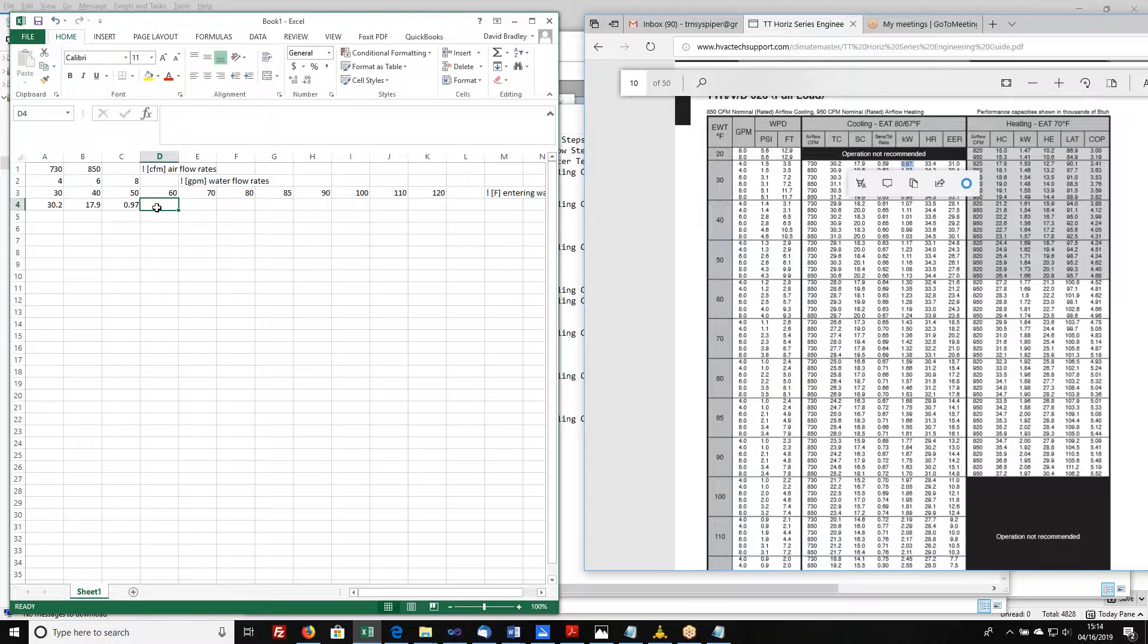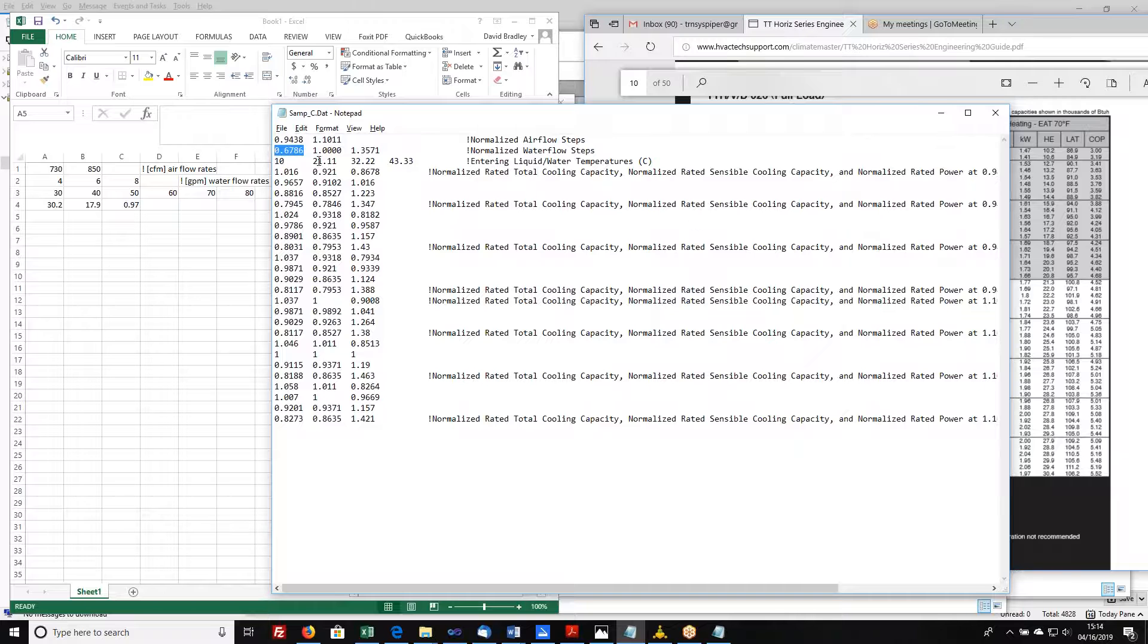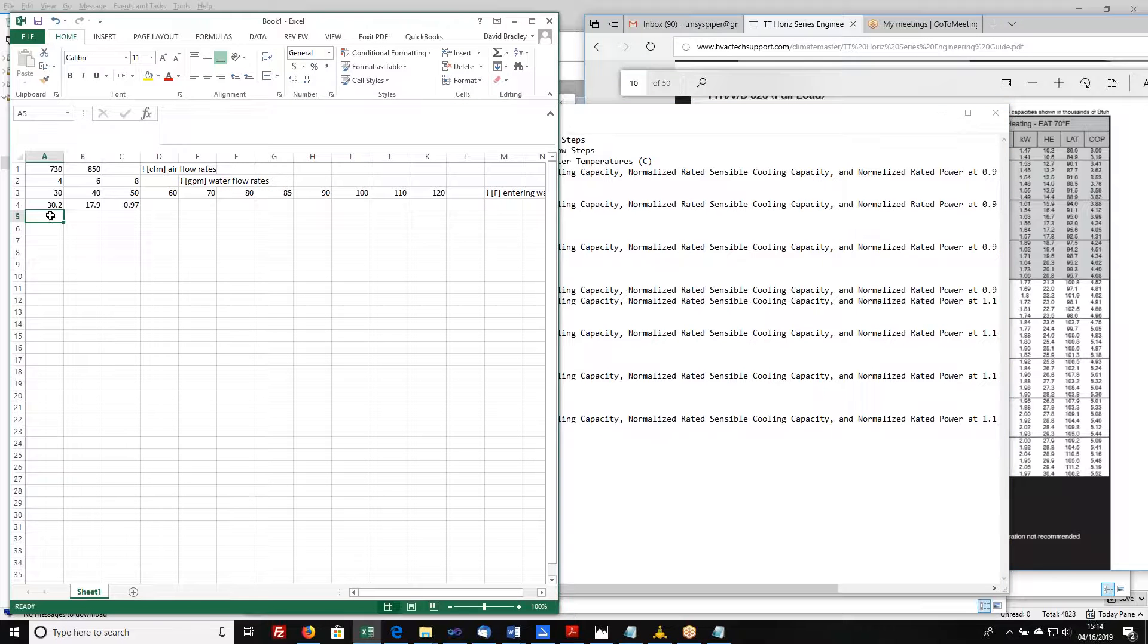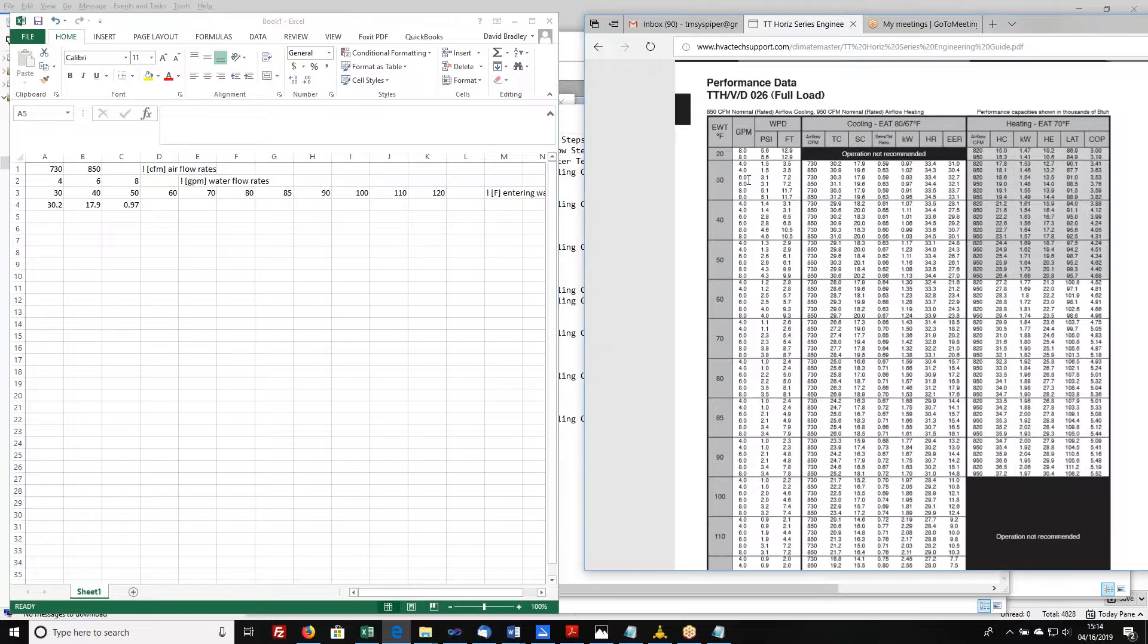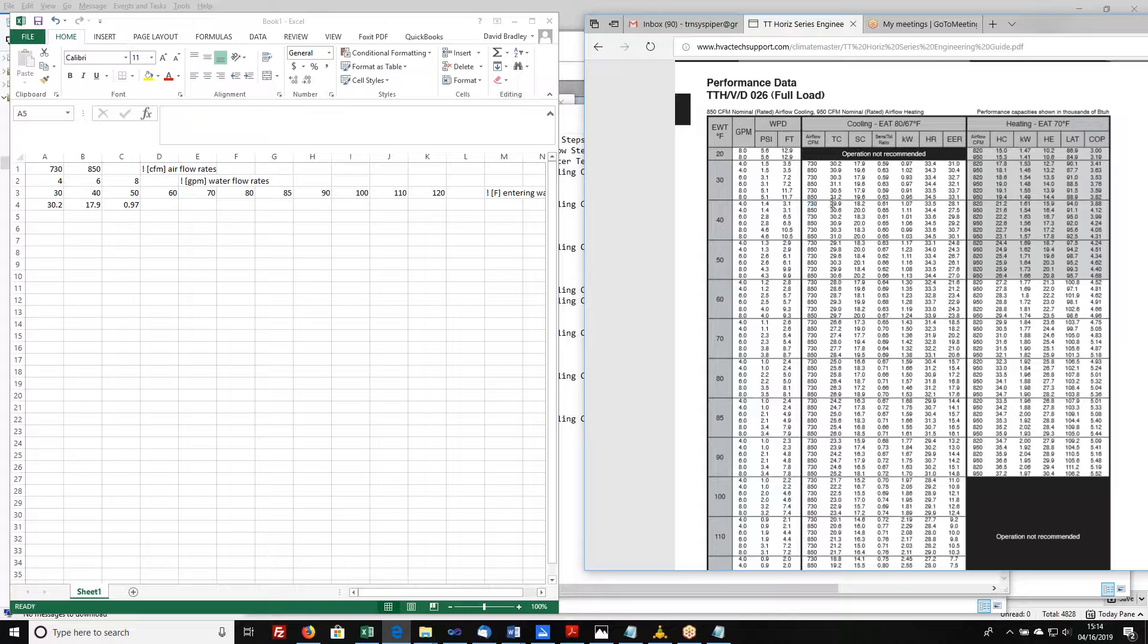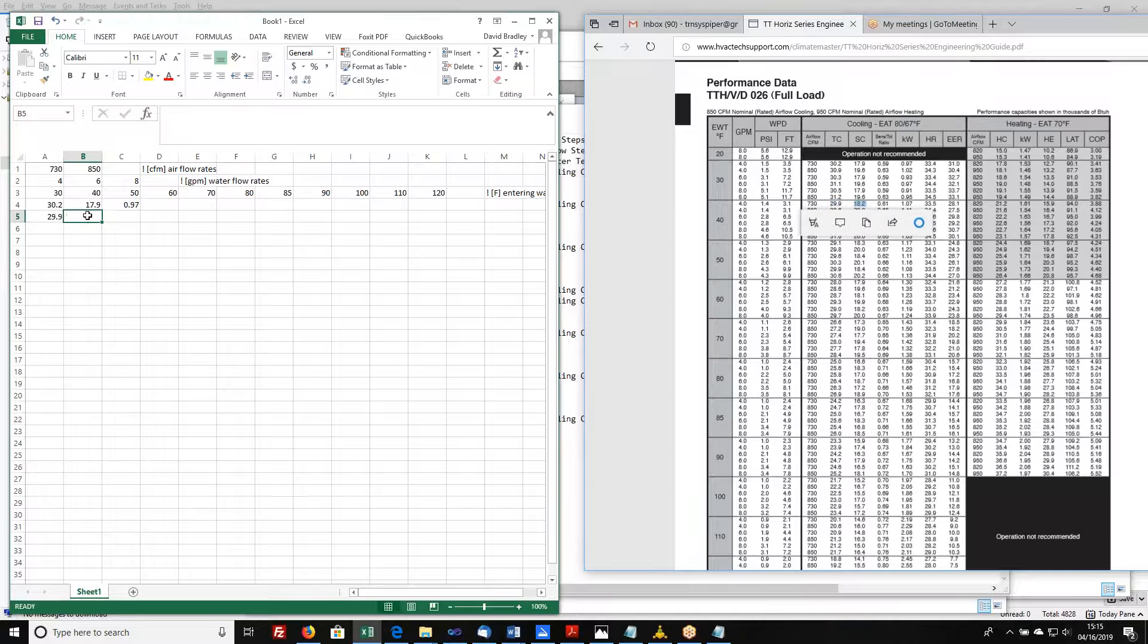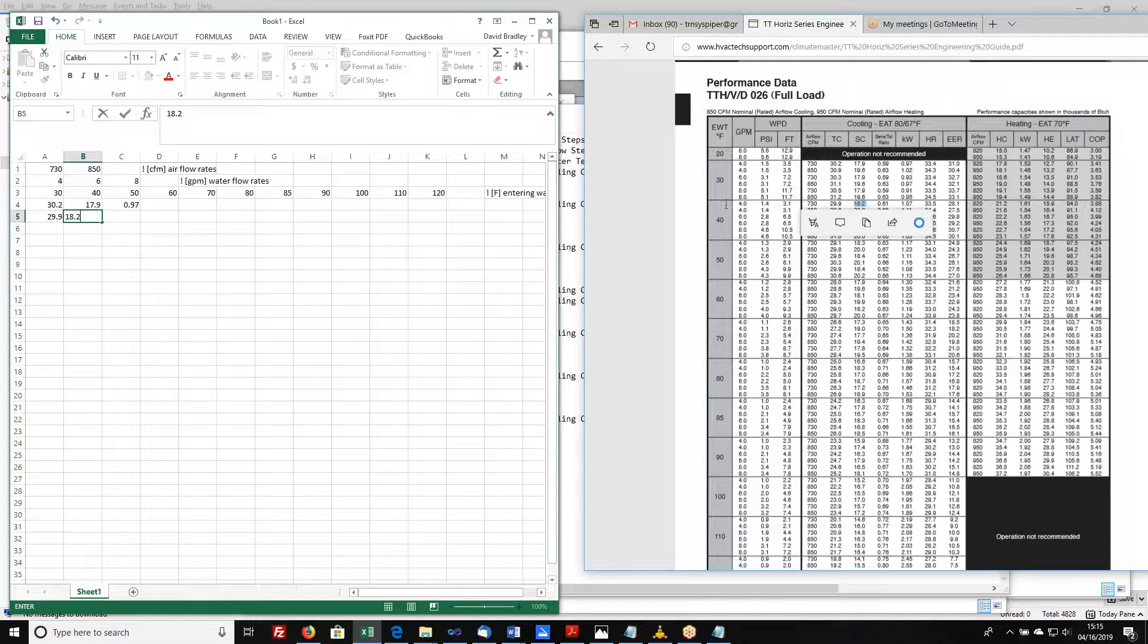We're going to normalize this whole thing later. We'll get to that in a minute. The second line corresponds to the first air flow, the first water flow, and the second entering liquid temperature. So let's go find those data. So now we've moved up to an entering water temperature of 40. I'm still at 4 GPM and 730 CFM. Now the total cooling capacity is 29.9. Sensible cooling capacity, 18.2. And the power has changed to 1.07.